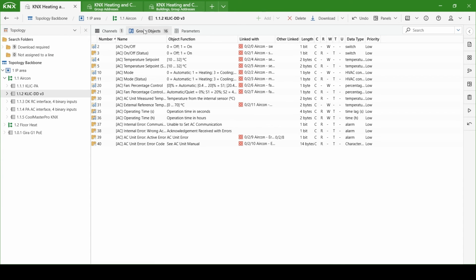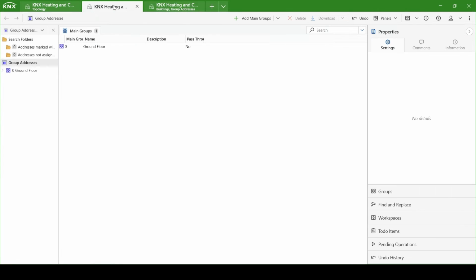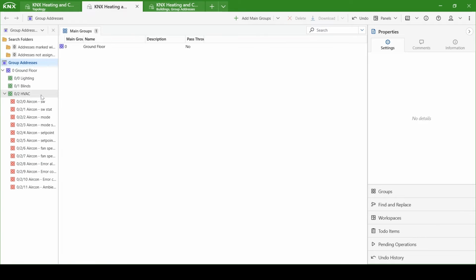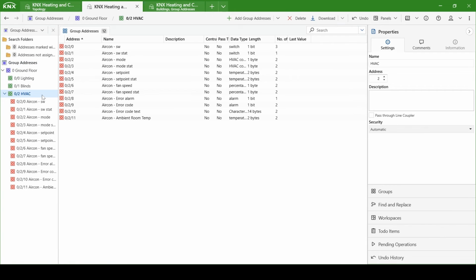Once you've done your configurations, you're left with your communication objects: the ability to turn on and off, set point, mode, fan speed, and I enabled the external temperature measurements coming through there. So I created some group addresses, some standard group addresses for air conditioning control, and we link those to the air conditioner interface to get full control of it.